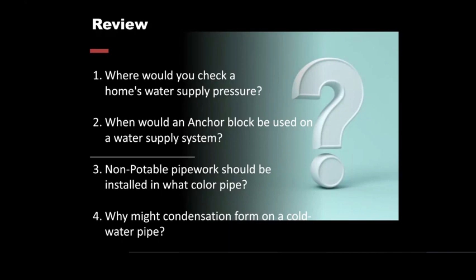The actual colour for a potable supply is forest green with a blue stripe as potable water. But obviously you're putting in whatever product you're putting in, domestic thing, you don't have to identify it. It's whatever colour the pipe is. Could be grey, could be black, could be copper colour if it is copper, could be metal. In a commercial situation, you're required to identify pipelines because otherwise it's just a pipe. There's a whole heap of pipe in a commercial building. If you can't obviously trace where it comes from, it's got to be labelled or colour coded.